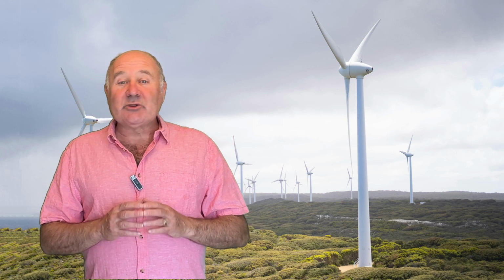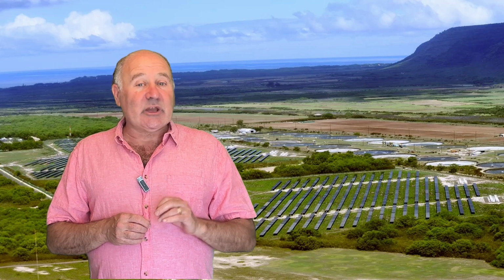No, this was a situation where the island of about 70,000 residents and 30,000 tourists were getting 60% of their power from the island's single oil-fired power plant, and it failed as the sun was setting. If not for the preparations that had been done, this would have brought the grid down for the entire island, as most of the rest of the power came from renewables through inverters.